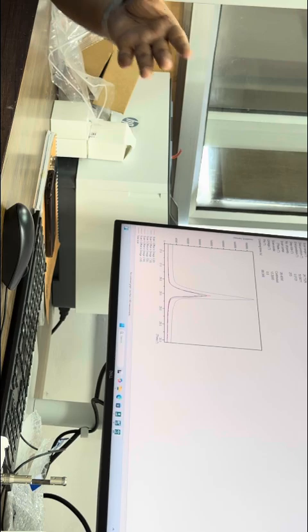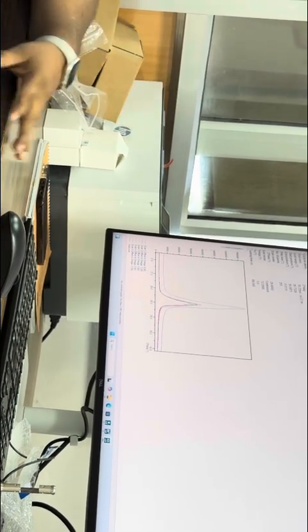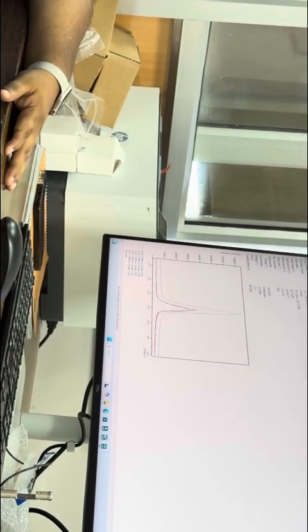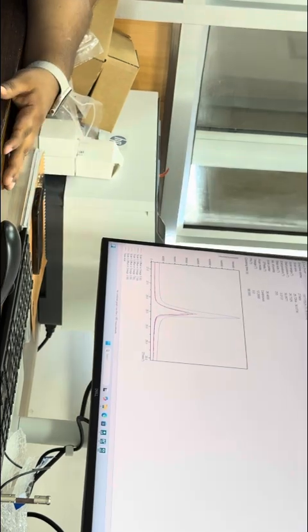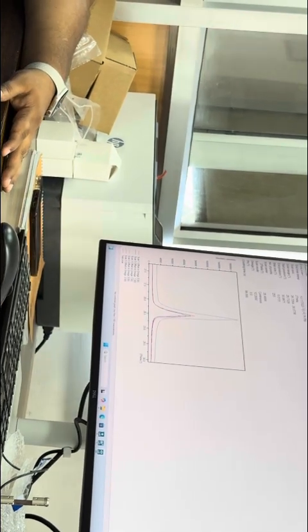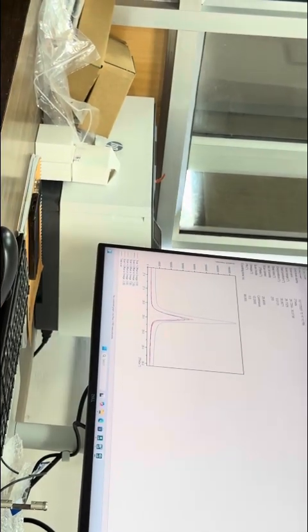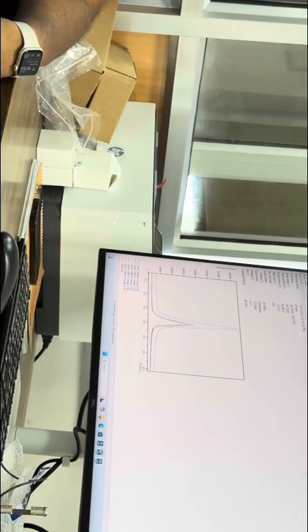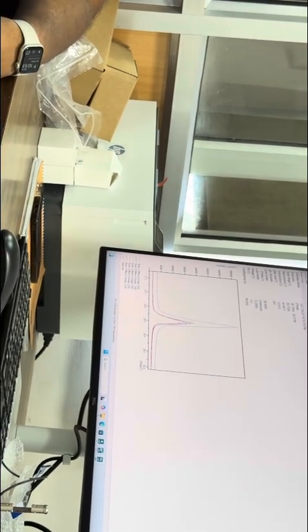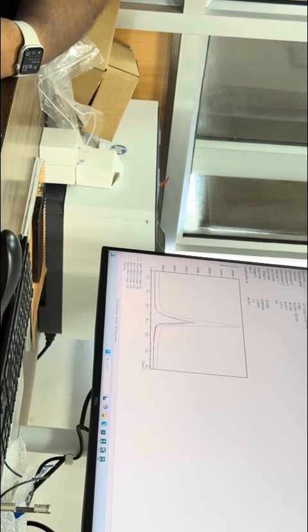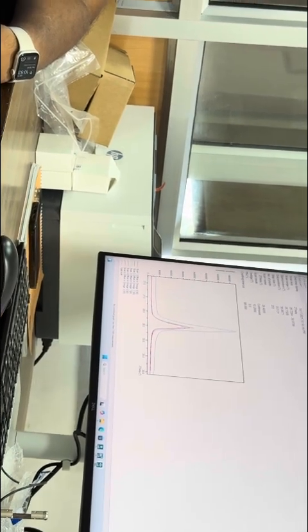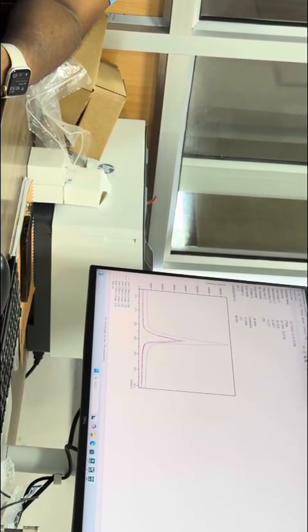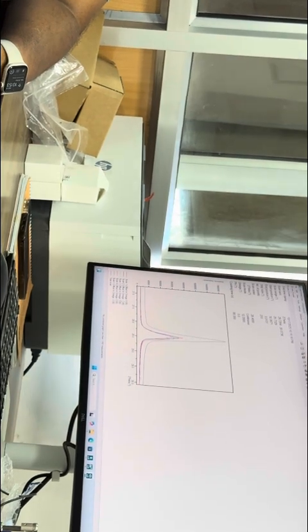You can increase the wobble range. How far can it go at maximum? Go to 3, 4, 5. 5 degrees is reasonable. Capturing -5 degrees is difficult for the detector. Usually crystallites are not misoriented by more than 5 degrees. If a crystallite is supposed to be like this, it can only have this tilt.